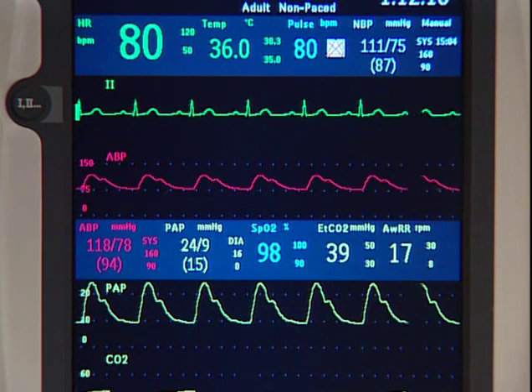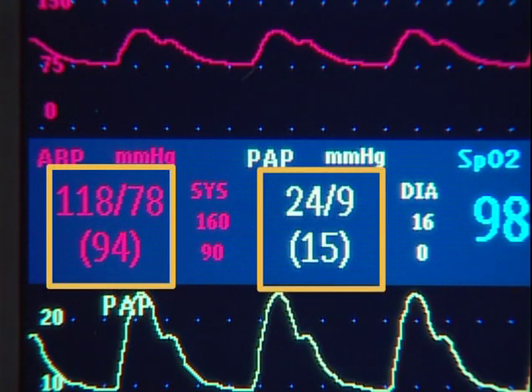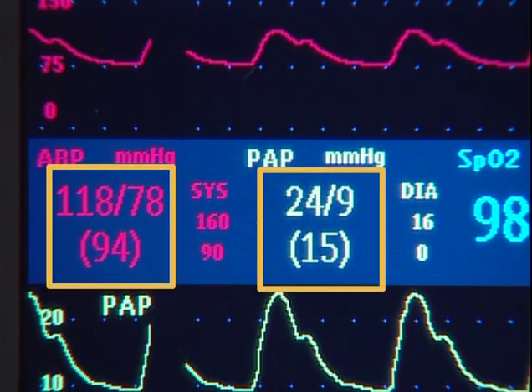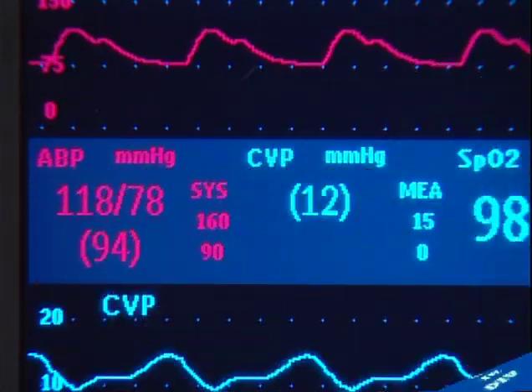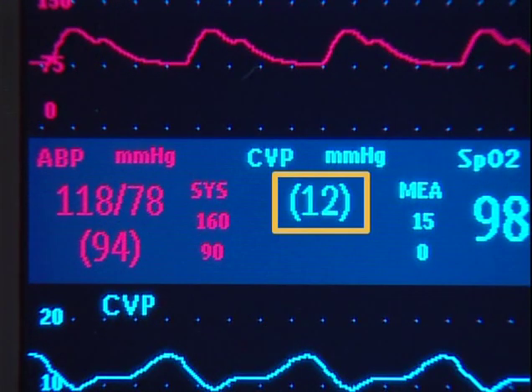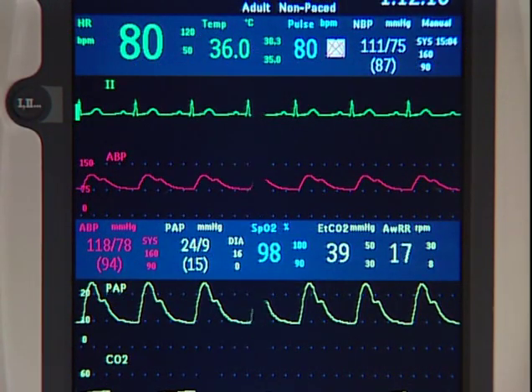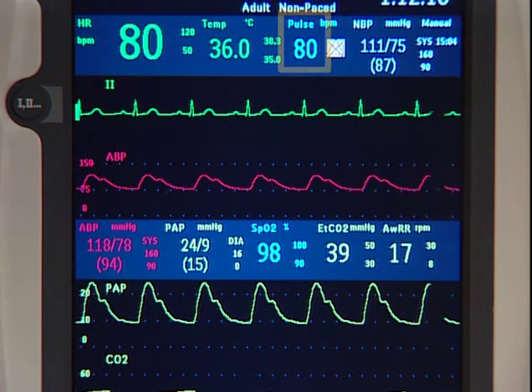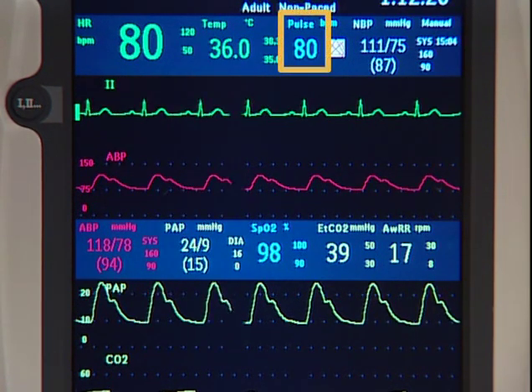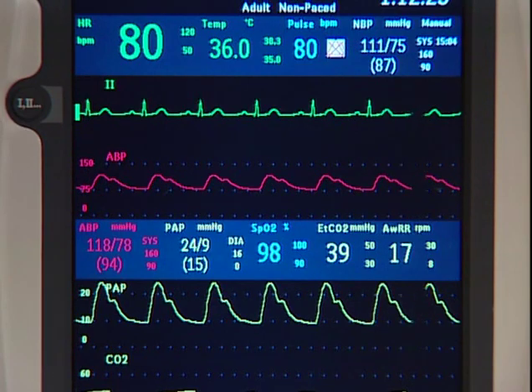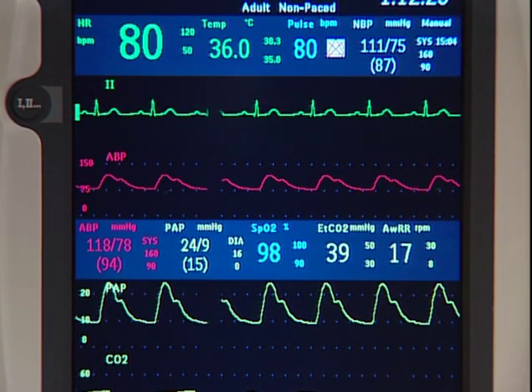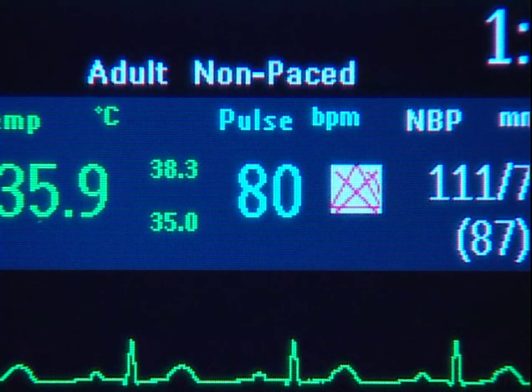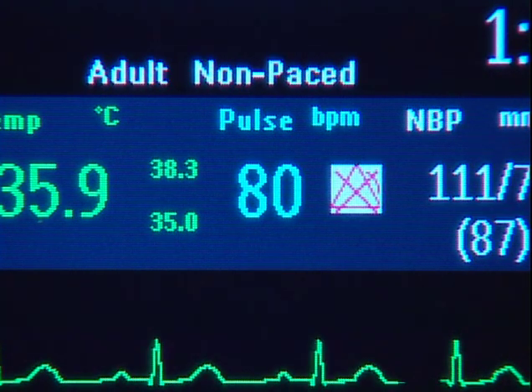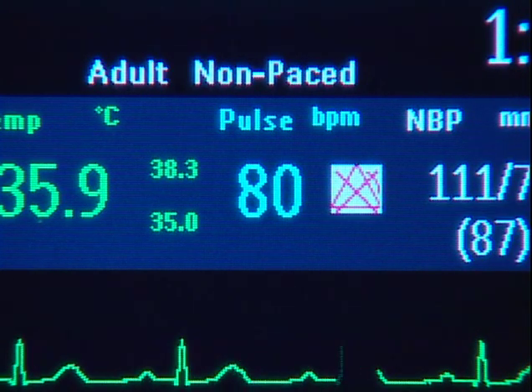If the pressure signal is pulsatile, numeric values are displayed for systolic, diastolic, and mean pressure. If the pressure signal is non-pulsatile, then only the mean is displayed. When both SpO2 and invasive pressure are present, the pulse measurement can be derived from either the SpO2 pleth wave or one of the 2 invasive pressures with pulsatile waves. The pulse value appears in the same color as its source. In this case, the pulse source is SpO2, indicated by its cyan color.